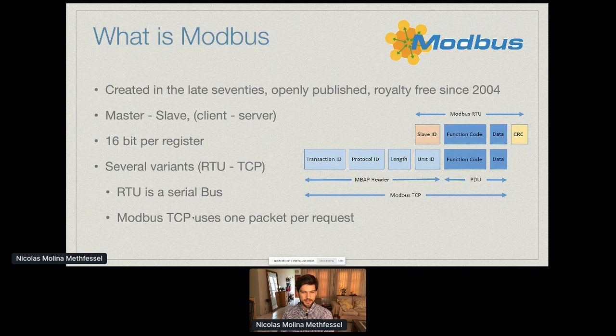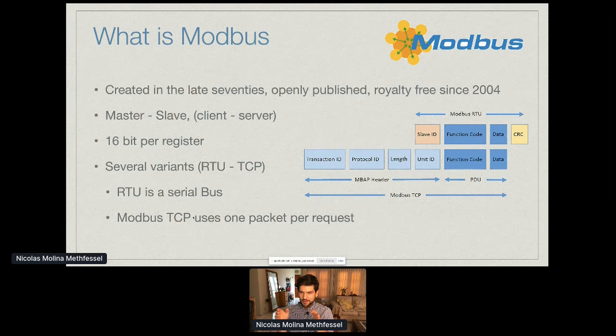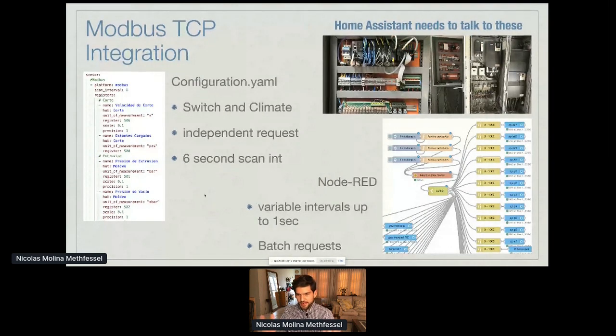There are two main variants — there are about seven, but the main ones are Modbus RTU, which is a serial bus. It works in Home Assistant but you need a bus adapter and a wire that goes from one device to the next. Then there is Modbus TCP, which came around when Ethernet became more widely used. It sends the same Modbus instruction wrapped inside an Ethernet packet — a very small register payload inside a complete Ethernet frame.